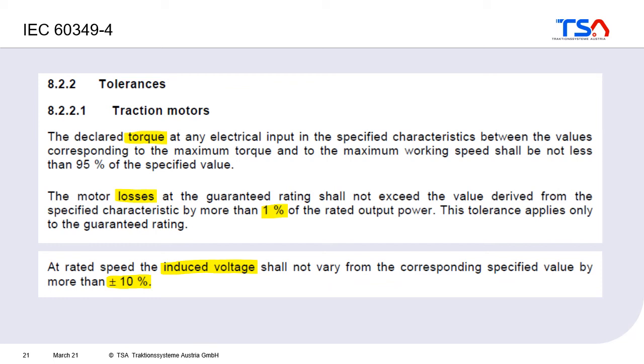The standard also defines allowed tolerances. For torque, it must not be less than 95% of the specified value. Motor losses must not exceed the specified losses by more than 1% of the rated output power. The induced voltage shall not vary more than ±10% from the specified value. Achieving these tolerances is not always easy, given manufacturing variations in magnet flux, magnet dimensions, and steel sheet dimensions.